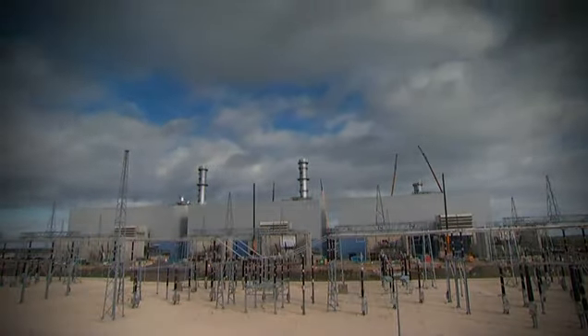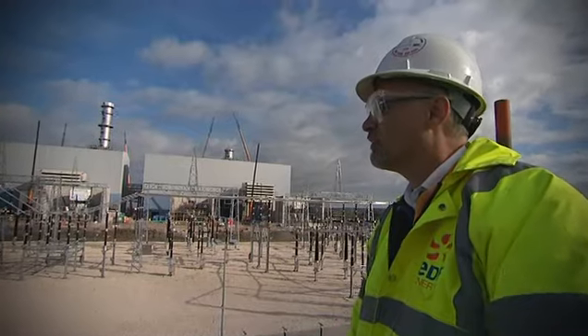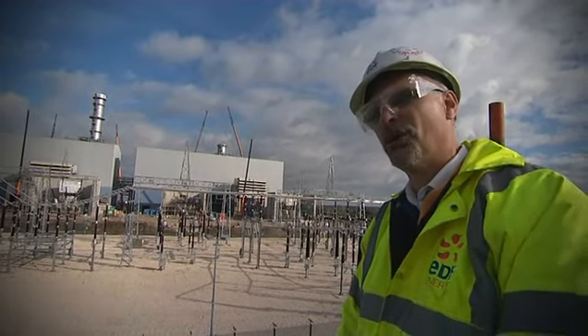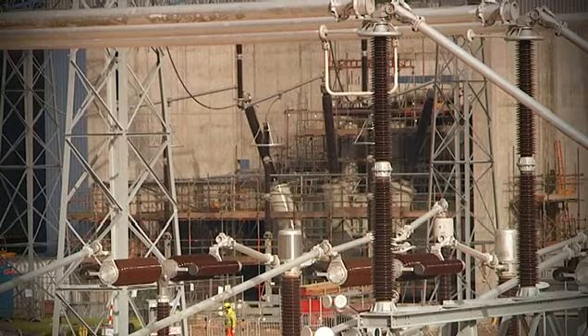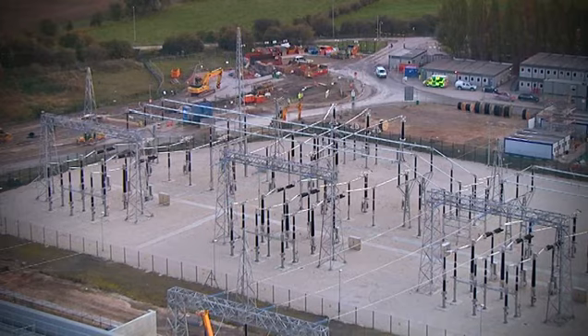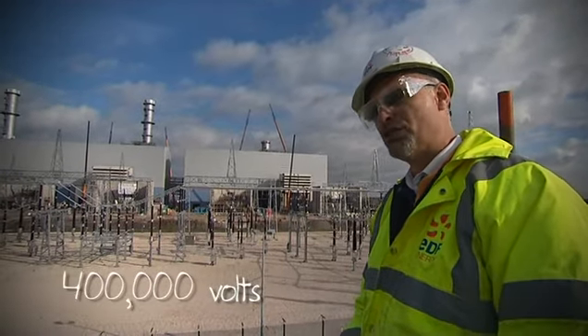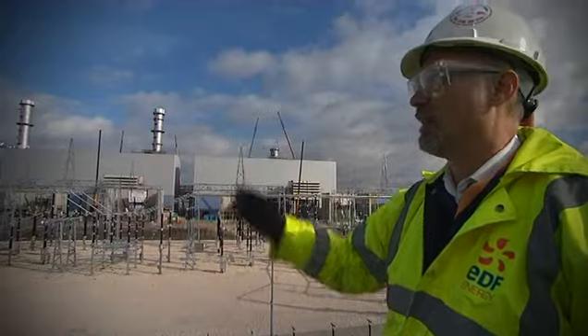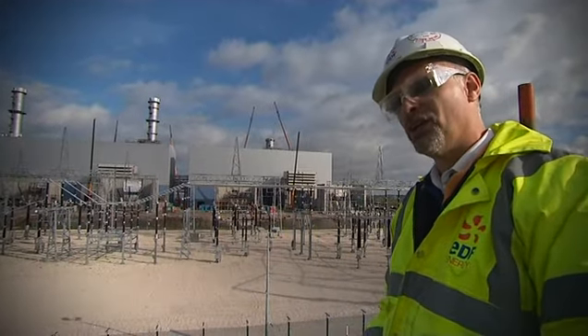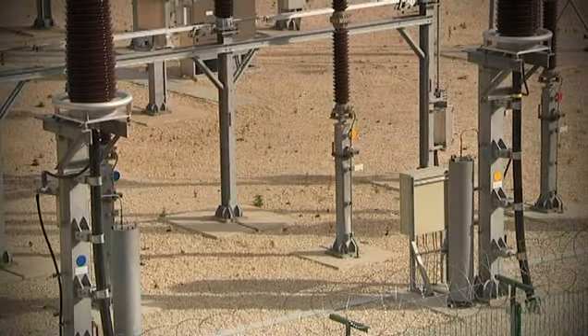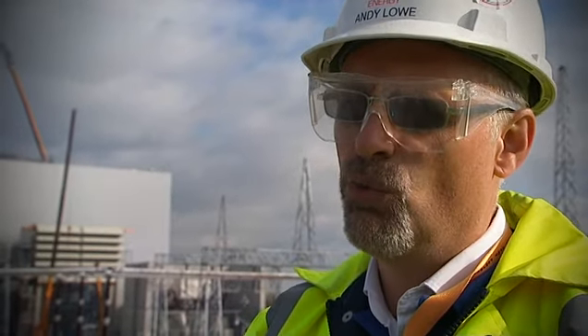This is the last part of the process, where we export power to the national grid. Power from both the steam turbine generator and the gas turbine generator comes out into the transformers. Voltage is lifted from 17,000 volts up to 400,000 volts, comes across the overhead lines into the switchyard and out through the 2 underground circuits. In effect, we've gone from 1 24-inch gas pipeline at the start of the process to 6 underground cables at the end of the process, and we've got all this in between.